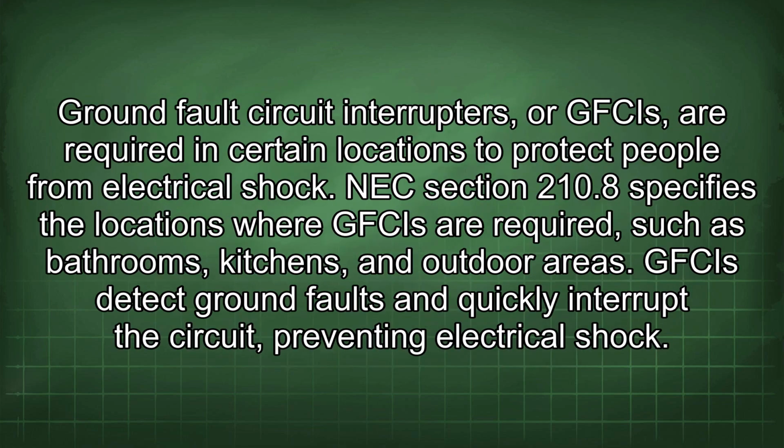Ground fault circuit interrupters, or GFCIs, are required in certain locations to protect people from electrical shock. NEC Section 210.8 specifies the locations where GFCIs are required, such as bathrooms, kitchens, and outdoor areas. GFCIs detect ground faults and quickly interrupt the circuit, preventing electrical shock.